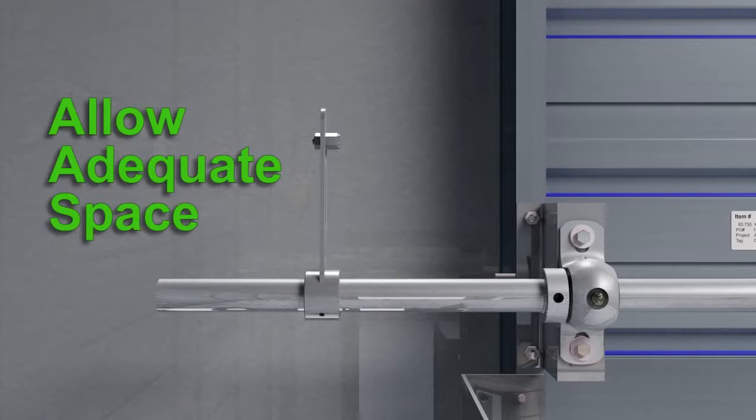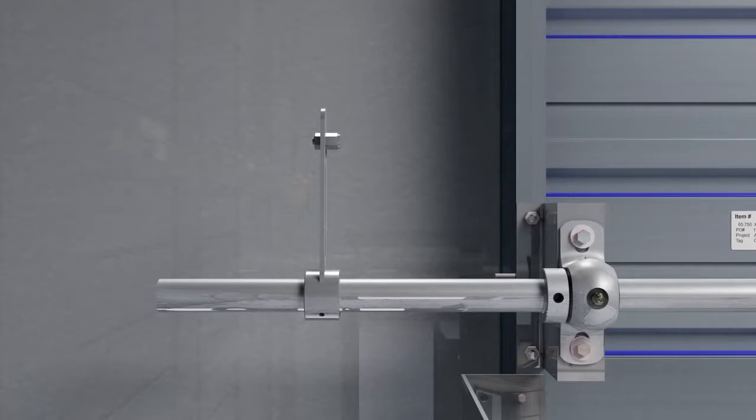Allow adequate space on the jackshaft for actuator mounting and service. A standard jackshaft extends 10 inches beyond the exterior of the damper frame. You can adjust this length by sliding the rod to the left or to the right.